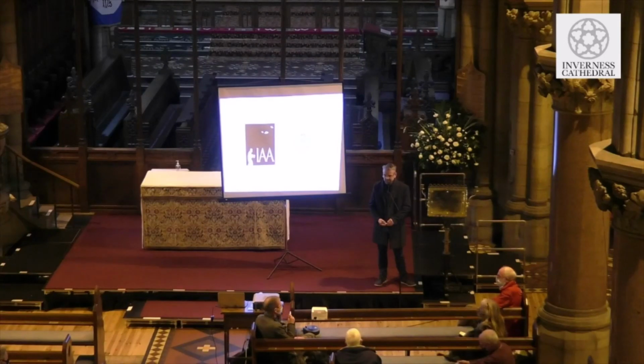But the one I had, as a matter of interest, when you're talking about roof ventilation: we're converting a building, you need roof ventilation. What do you need roof ventilation for? Well, there's no vents, and when we actually looked at the roof, it was 180 years old, there was no felt in it. So we said, we'll do an air tightness test in the attic and prove that we don't need to do ventilation.